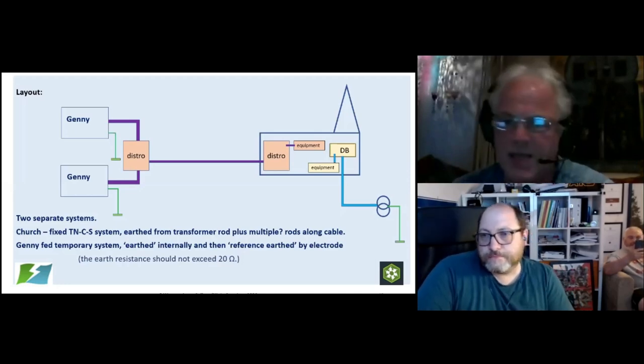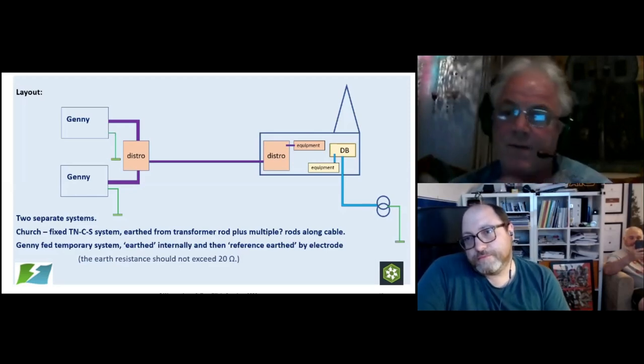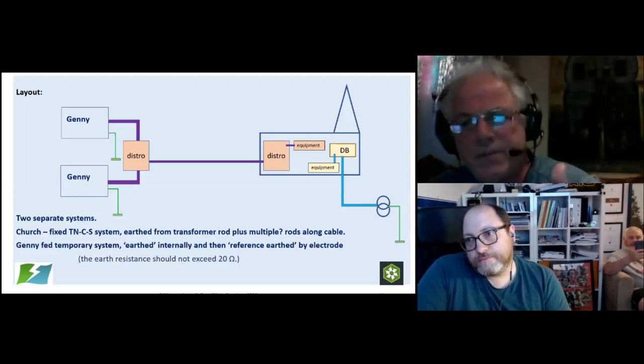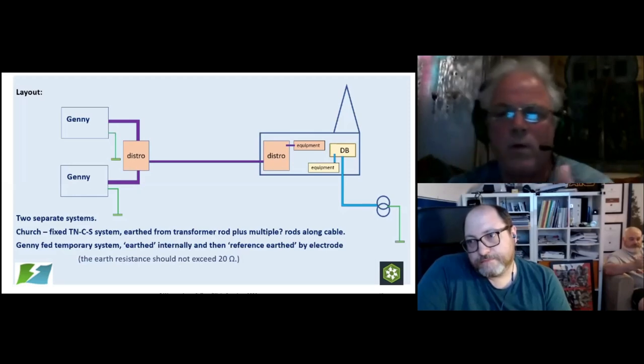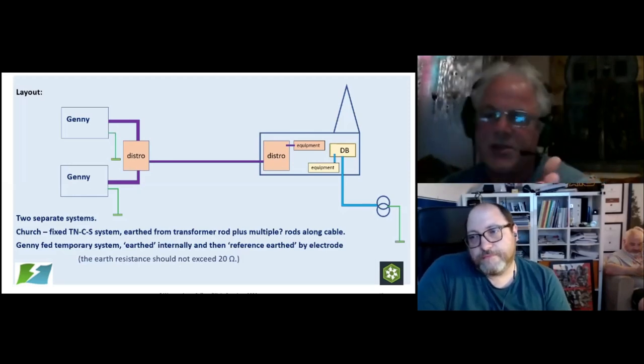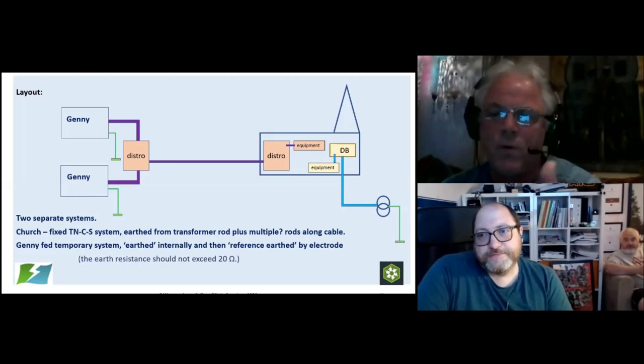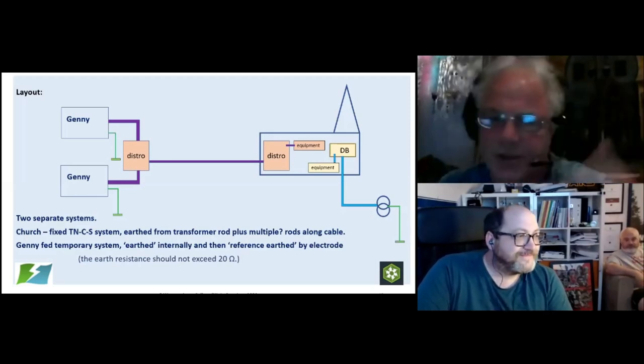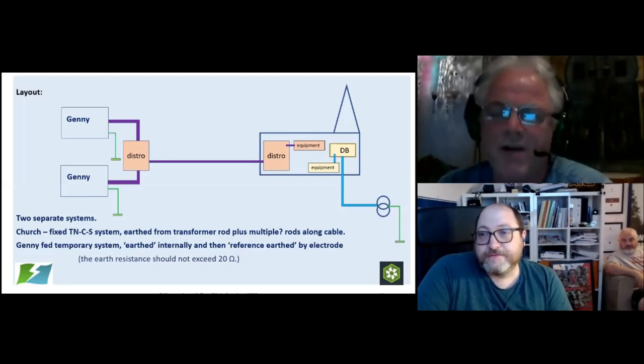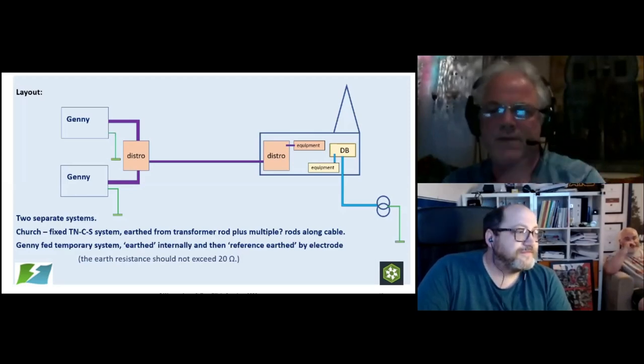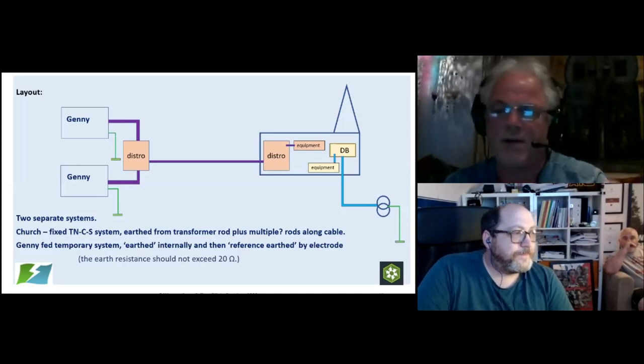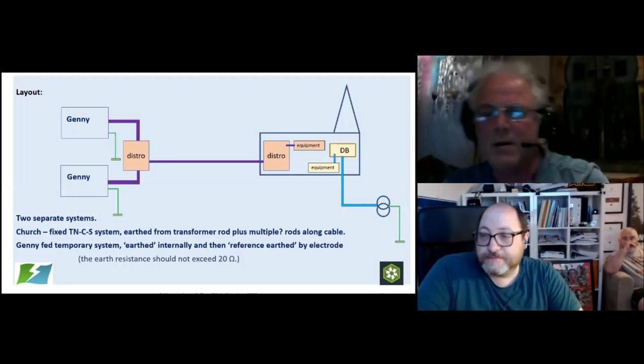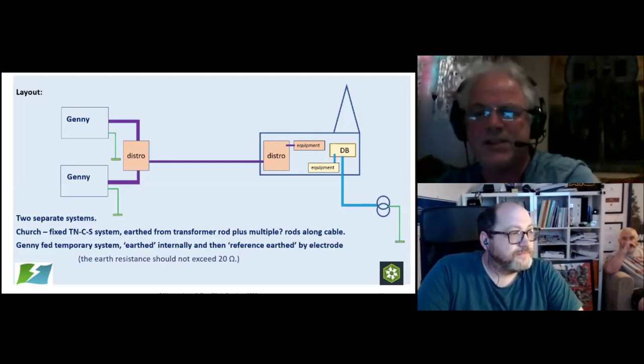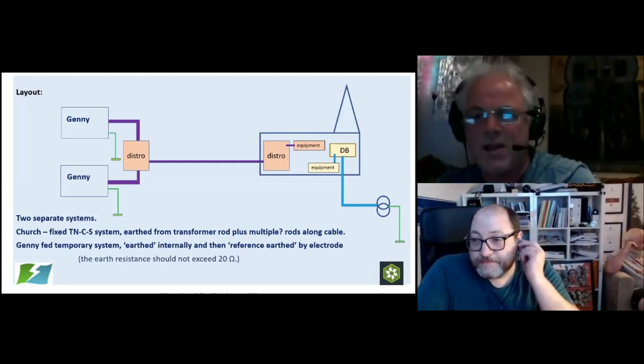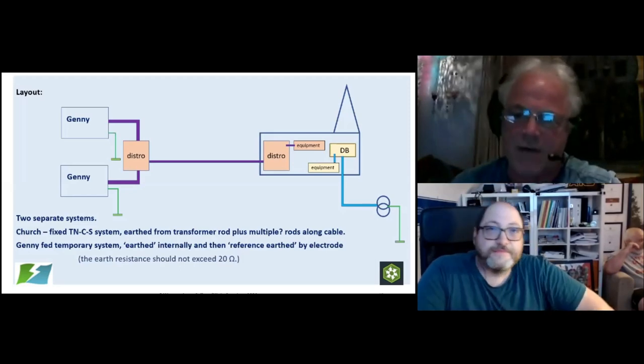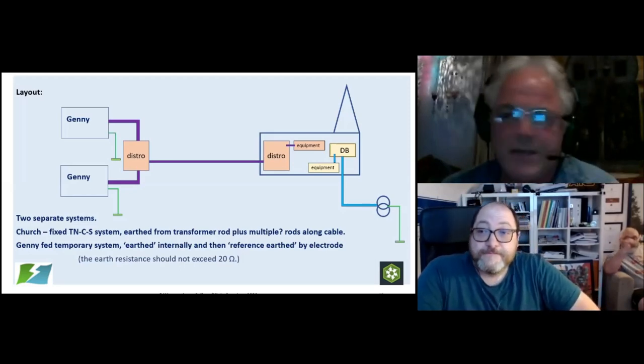Now, I totally understand, I think somebody's mentioned it, that if you had a fault on the system and there was an issue with the other system, would the fault current then tend to want to go back down the other system? So you end up with a fault going from, for instance, the equipment provided by the generator. You have an earth fault on a piece of equipment, and then there's a break in the earth to the generator. So instead of going that way, it goes back through the fixed installation earth, back into the ground, and then through the ground back to the earth electrode of the generator, and then back up that way. Now, yes, it could happen.